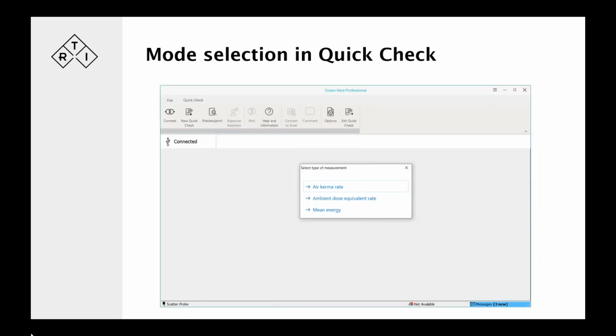It works also with the QuickCheck software, where you can select the mode of operation that you're facing. So it's either the air kerma rate, which gives you gray or Röntgen, or the ambient dose equivalent, which gives you the Sievert values for it. There's also one not so much in use, but the possibility to measure and to determine the mean energy of the spectrum that you're facing with the leakage.